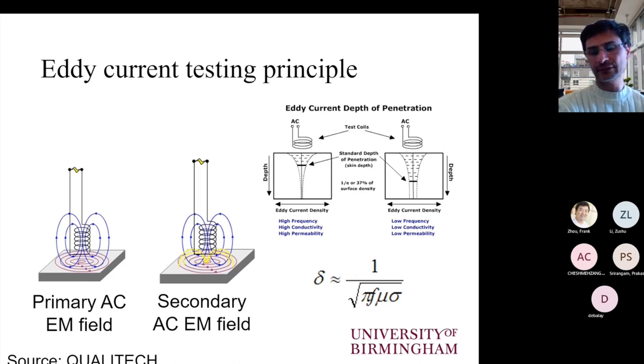What we have to take into account when we are doing eddy current inspection is the empirical equation that relates the penetration depth of the inspection with the frequency, the conductivity of the test piece, and the relative magnetic permeability. So in the case of non-ferrous materials, we can ignore mu. So mu will not play a role. It's just the conductivity and the frequency that we need to take into account. So the higher the frequency, the higher the conductivity, the lower the depth will be.